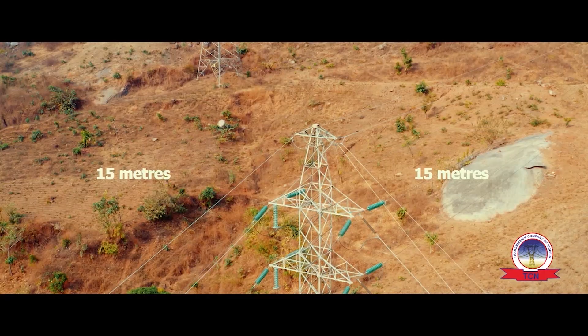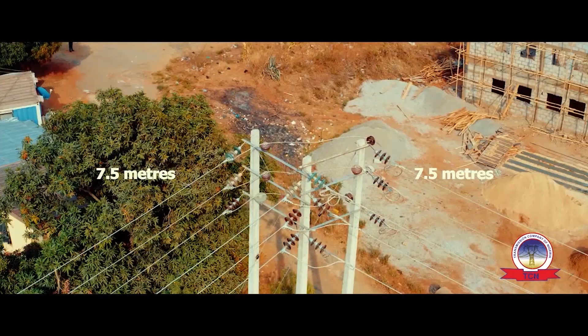Oga, we are talking of a burnt house and you are talking of right of way. What is right of way and safety compliance? Safety compliance simply means before erecting any structure around any electricity tower or line, there are safety distances you must adhere to. These safety distances are 25 meters on both sides of the tower for a 330 kV line, 15 meters for a 132 kV line, and 7.5 meters for a 33/11 kV line. These stipulated safety distance instructions are what we call right of way.